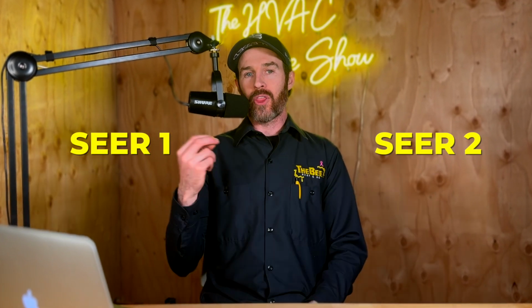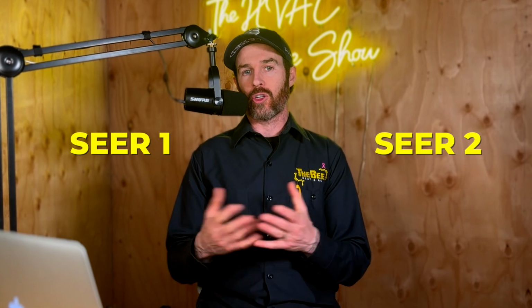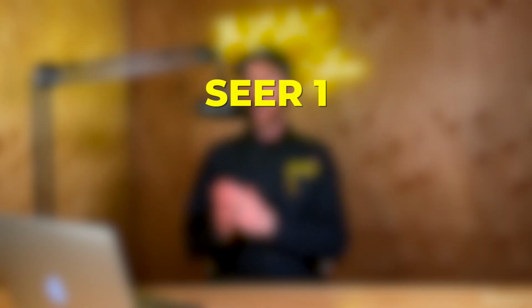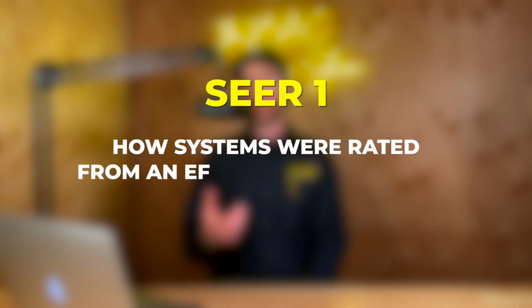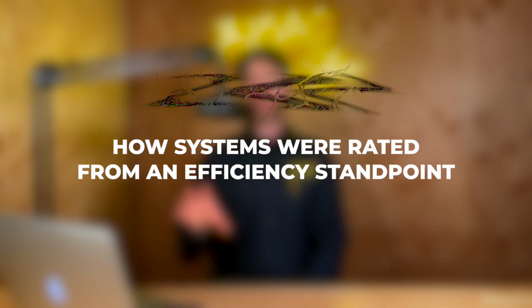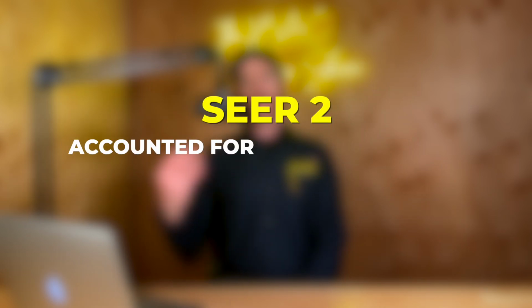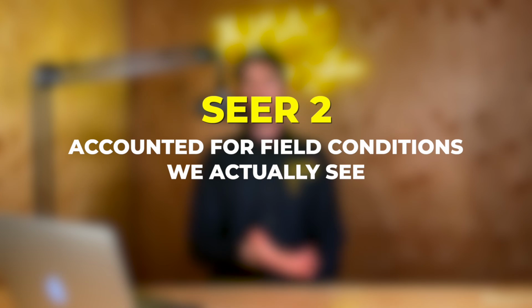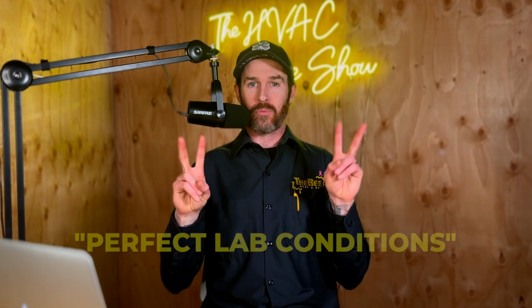If you're not sure what that means, there were a few minor changes between SEER 1 and SEER 2, but the biggest one, when it came to how systems were rated from an efficiency standpoint, was that SEER 2 accounts for field conditions we actually see when we're in the field, versus perfect lab conditions when testing a system's efficiency.